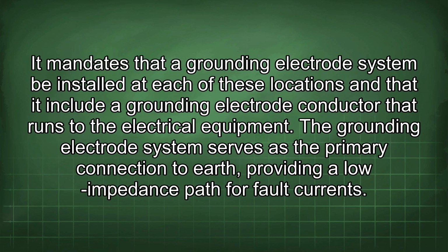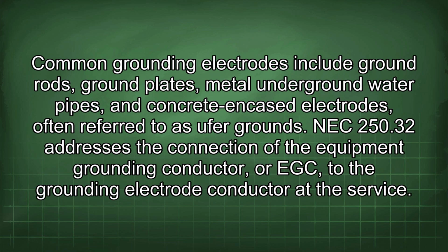It mandates that a grounding electrode system be installed at each of these locations and that it include a grounding electrode conductor that runs to the electrical equipment. The grounding electrode system serves as the primary connection to earth, providing a low impedance path for fault currents. Common grounding electrodes include ground rods, ground plates, metal underground water pipes, and concrete encased electrodes, often referred to as UFER grounds.